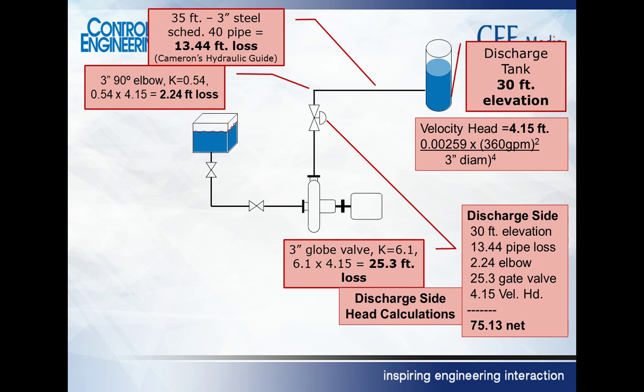We've got 30 feet of elevation, so we have to pump that liquid up 30 feet. We have to get it moving a little faster, so we put some velocity head in. We've got 35 feet of pipe, and it's only 3-inch pipe, so we lose 13 feet of head through the pipe. We've got an elbow, which loses a little bit. We've got a globe valve, and the globe valve loses 25 feet of head.